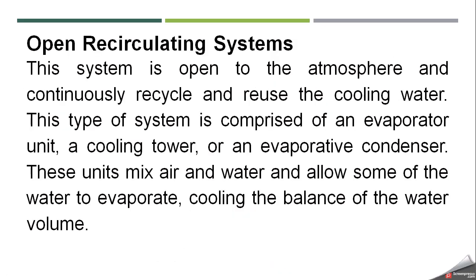The third type is the open recirculating system, which is open to the atmosphere and continuously recycles and reuses the cooling water. Although it recirculates, one end is open to the atmosphere where it rejects heat. This type of system comprises an evaporator unit, a cooling tower, or an evaporative condenser. These units mix air and water and allow some of the water to evaporate, cooling the balance of the water volume because evaporation causes a drop in temperature.